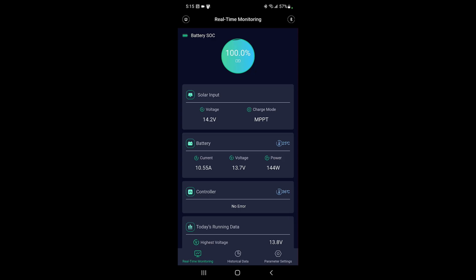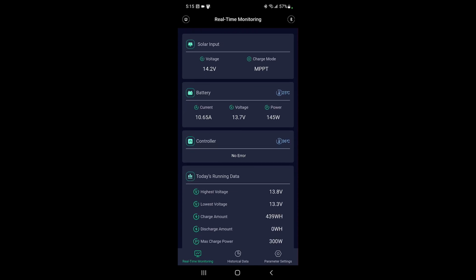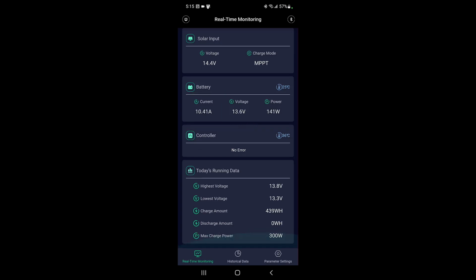As you can see in real-time monitoring, going from one section to the other, on solar input we're currently getting 14.2 volts. That's important because that voltage has to be higher than the battery voltage, currently set at 13.7 — that's how much it's getting from the charge controller. On the battery side, we're getting just over 10 amps and 140 watts.